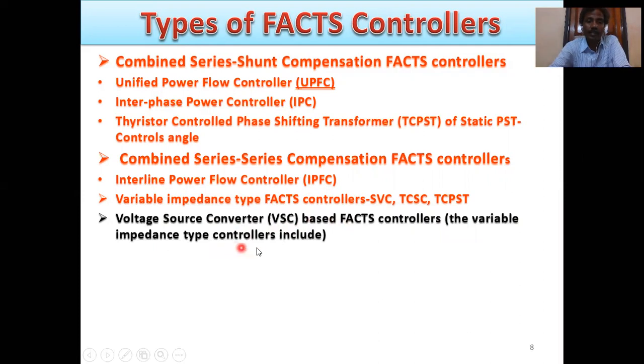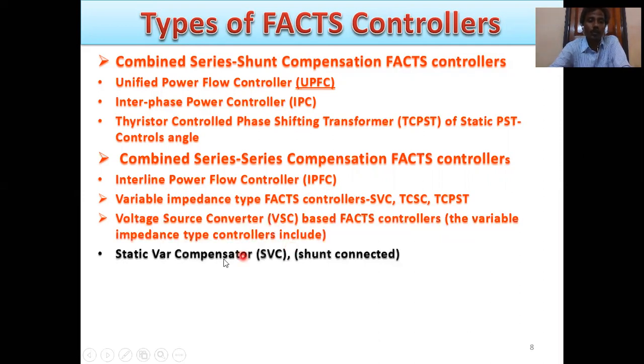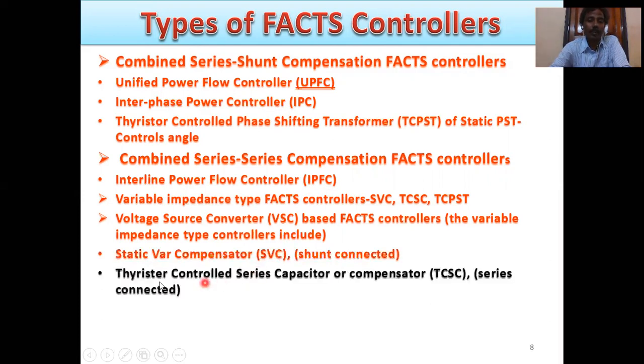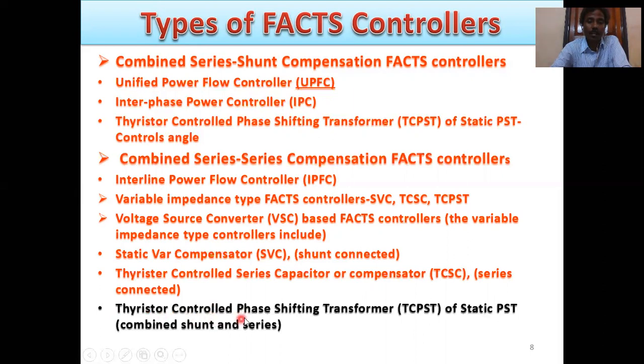The variable impedance type controllers include the static VAR compensator, a shunt connected FACTS controller. Thyristor controlled series capacitor or compensator, TCSC. This is a series connected FACTS controller. Thyristor controlled phase shifting transformer, TCPST or static PST, a combined shunt and series controller. This is the shunt and series controller, TCPST.